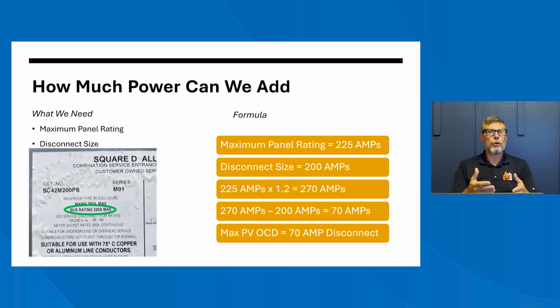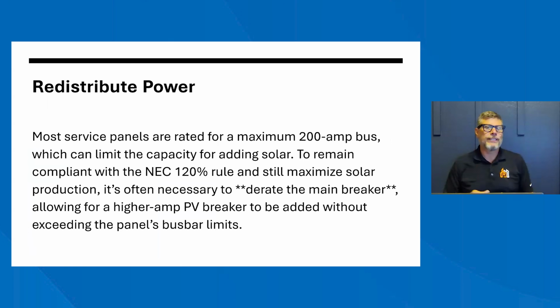Now, what do we do if we go to a panel and it says we have a 200 amp max bus and a 200 amp disconnect? We can only have a 40 amp disconnect in there, but we've got a 65. Well, how do we fix that? The way we fix that is through redistributing the power. It's also called derating the main breaker. So we're going to use our 120% rule, and we're going to derate that main breaker down to something that will allow that 65 amp breaker to be acceptable in that panel. So we would derate the main breaker down to 175 amps. When we do that, that gives us an extra 25 amp headroom, allowing us to have that 65 amp breaker in that panel for that solar array, which keeps us within that 120% rule.